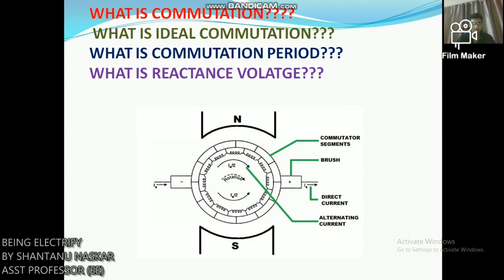When commutation takes place, the coil undergoing commutation is short-circuited by the brush. The brief period during which the coil remains short-circuited by the brush is known as the commutation period, denoted by Tc. If the current reversal is completed by the end of the commutation period, it is called ideal commutation. If the current reversal is not completed by that time, then sparking occurs between the brush and the commutator, resulting in progressive damage to both.